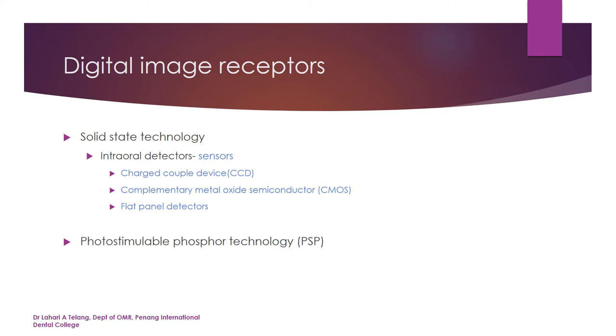Various receptors are available in the market for use as digital radiology dental sensors. They are broadly divided into solid state technology and photo-stimulable phosphor technology, also called PSP. Solid state detectors or sensors can either be charged coupled devices (CCD), complementary metal oxide semiconductors (CMOS), or flat panel detectors. Among these, CCD, CMOS, and PSP are the most popular in the market.